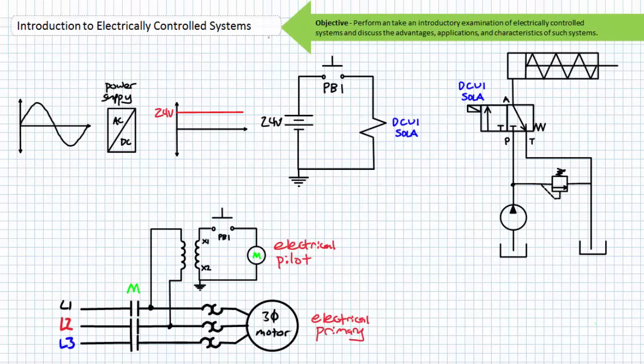Similarly, a means of differentiating between the pilot and primary aspects of an electrically controlled system incorporating motors must be used. Again, there must necessarily be two schematics for this system, one being the primary electrical schematic, the other being the electrical pilot schematic. If the pilot and primary schematic are to be illustrated on the same sheet, ordinarily the pilot is drawn in thin lines and the primary in thick lines, although this sometimes isn't the case.